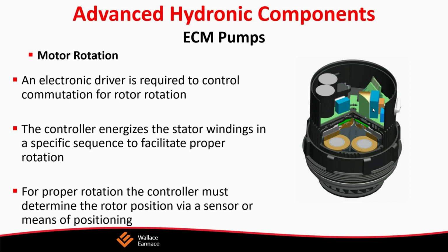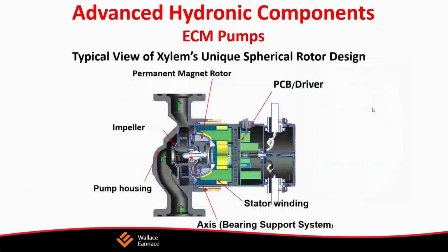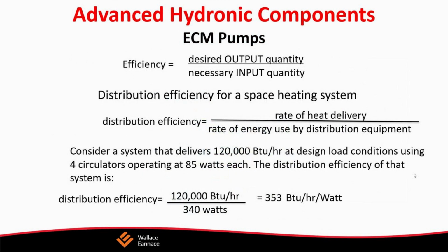They have permanent magnet rotors. The magnetic rotor grabs onto the rotating stator magnetic field and causes rotation. This rotation is controlled by a microprocessor, which keeps the stator current in phase with the magnetic pole of the rotor. Thus, you end up with much lower current requirements, no slip, and much greater efficiencies. With this permanent magnet motor technology, the rotor is a permanent magnet, and commutation is the process of pulsing power on and off to create a rotating magnetic field in the stator. As you can see here, as the stators are drawing, the rotor is being attracted to the various points on the stator. And inside, you need an electronic driver to control this commutation for the rotor rotation.